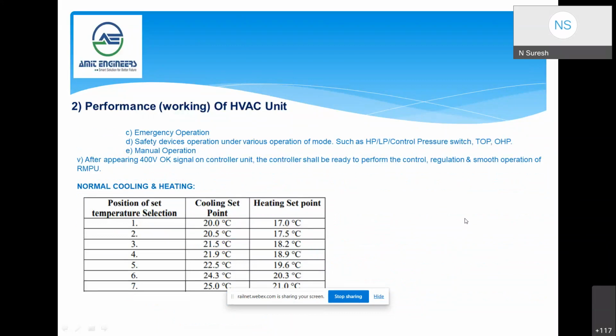Other than the normal operation, there are safety controls, like a pressure transducer as well as high pressure and low pressure switches, thermal overload protection, and overheat protection switches in the system. Whenever the TOP opens or the OHP opens, the signal will be given to the microprocessor controller and a fault is generated immediately. And this train has an additional feature. The faults will be passed on to the TCMS display, so that needed action can be taken in case of any emergency or any fault. It can be addressed in the workshops.